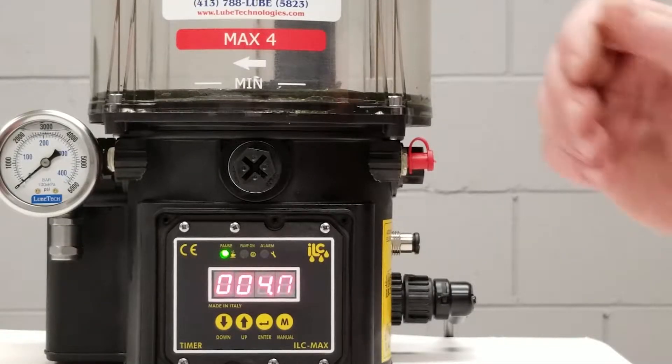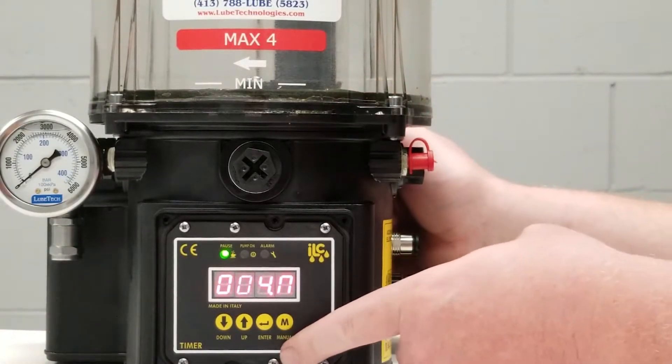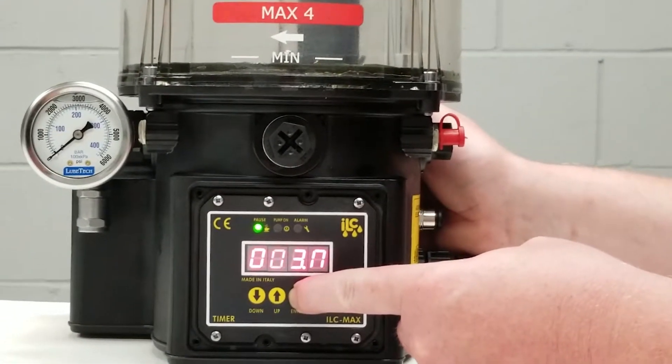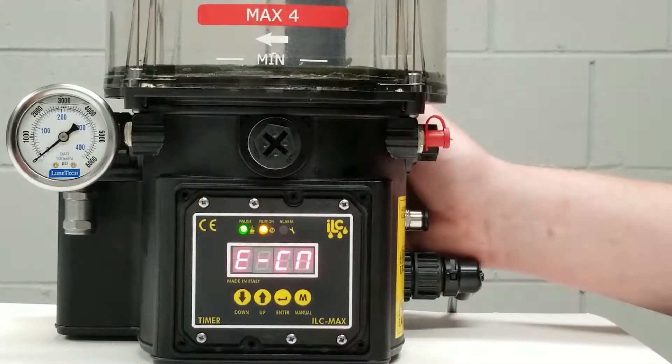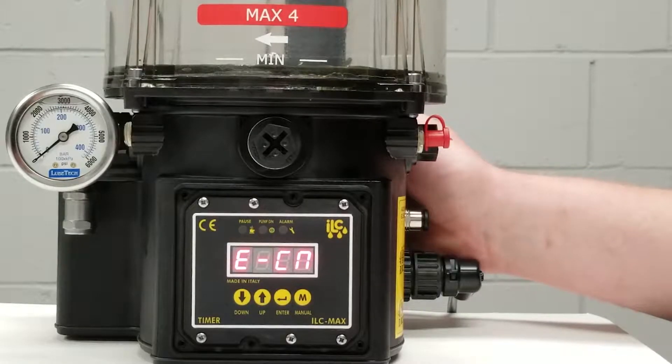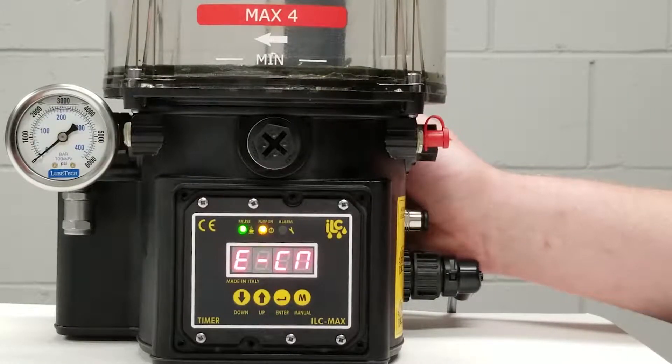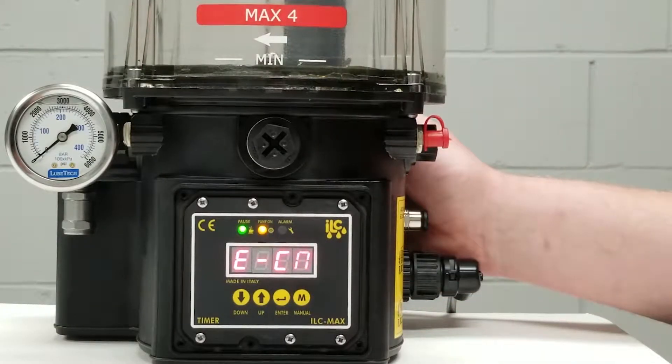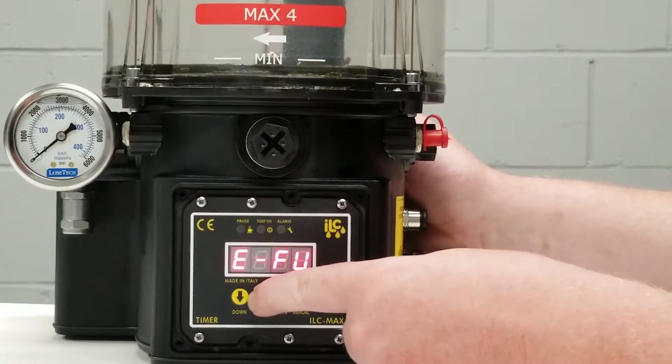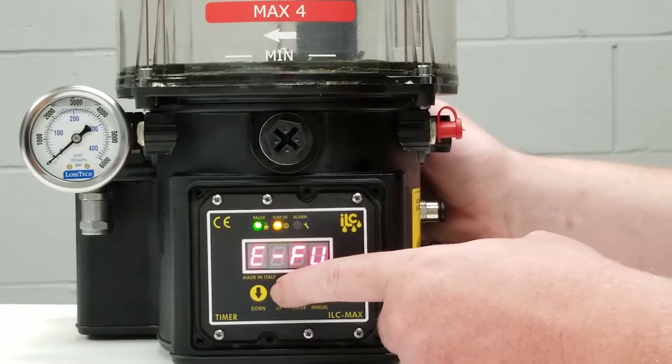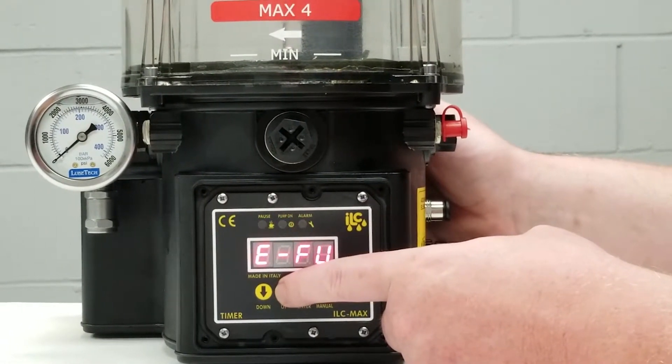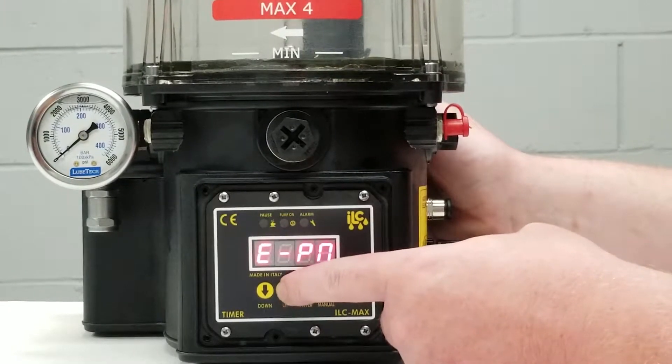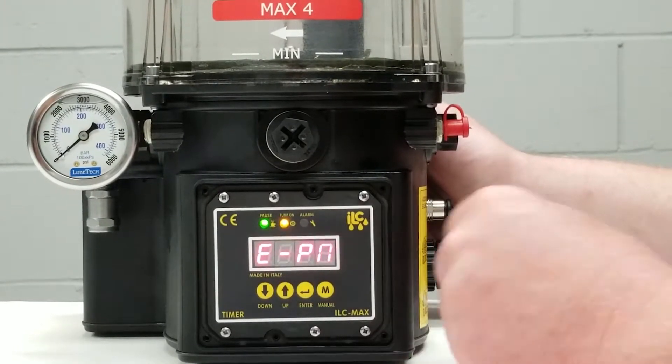So let's enter the programming mode. We do that by simply pressing and holding the enter key for approximately three seconds and that's going to take us to E-CN. From there I simply need to press the up button to go through my pump's pre-programmed status. E-FU just tells me that I'm going into the programming mode and your first parameter will be E-PN.